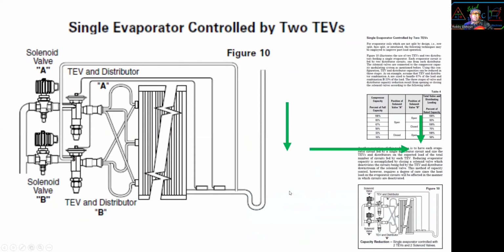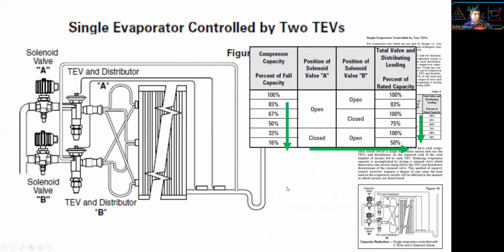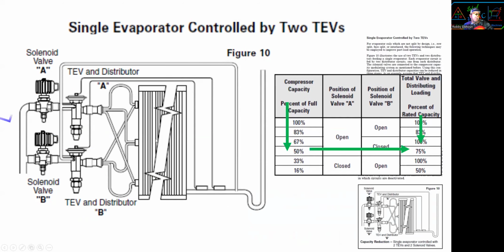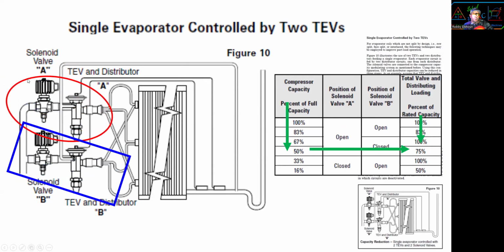Next, we have a single evaporator controlled by 2 expansion valves. All right, now we have A and B, red and blue. And then if we want the compressor running 50%, we'll open the A valve, close the B valve, and that will leave us 75% capacity. This is very rare. I just figured I'd mention it because it's really cool. I've never seen 2 expansion valves controlling 1 evaporator, but you learn something new every day. That's why HVAC is so cool.